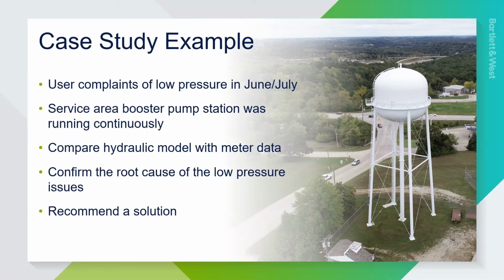So we got this problem, and instantly, being engineers, we had a lot of questions. What was the peak month for that area? What was the peak day usage? Do we have the ability to obtain any instantaneous peak data to correlate to our demand diversification model? And then the last question is, where is the water going? Who's all using water? Is it just this farmer? Is this largely spread across the service area or multiple service areas?